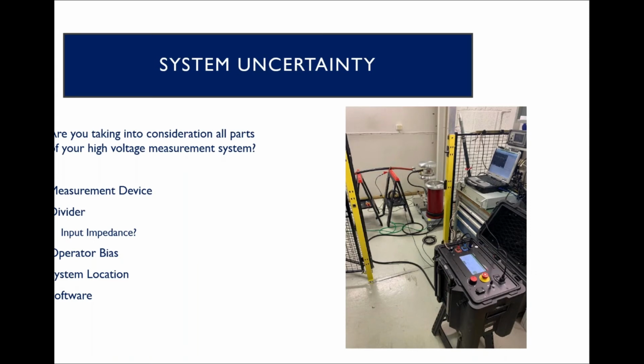So while minimizing the sources of error we previously discussed, there are plenty of other sources that may not be able to be minimized or may not even be considered. So one of the things you should always ask yourself when making a high voltage measurement is, are you taking into consideration all the parts of your high voltage measurement system? With the measurement device, this is the device or tool you are reading your measurement from. It's sure to have some level of error that's inherent to the product, and that should always be applied to your total system uncertainty. If you're using a divider, for example, as well, this typically also has its own level of error, which will need to additionally be considered.